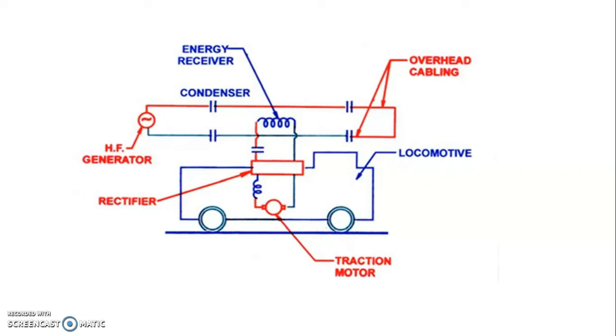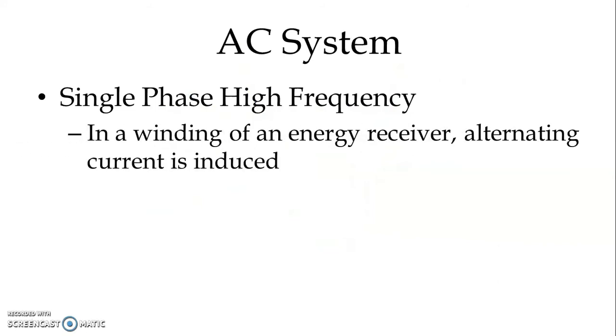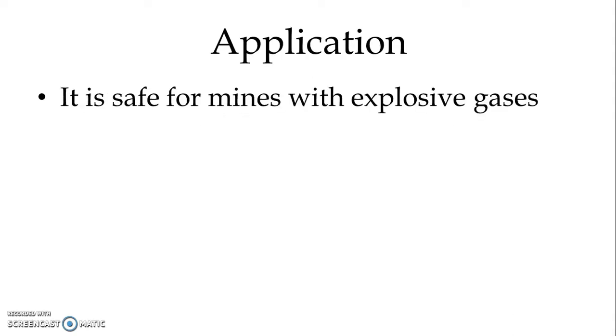The winding of the energy receiver is kept 40 millimeters away from the overhead cables. Alternating current is induced in the winding of the energy receiver, and the induced AC voltage is then rectified at the locomotive and fed to the DC traction motor. This system is safe for mines with explosive gases because it is contactless conduction of current, and sparking is avoided.